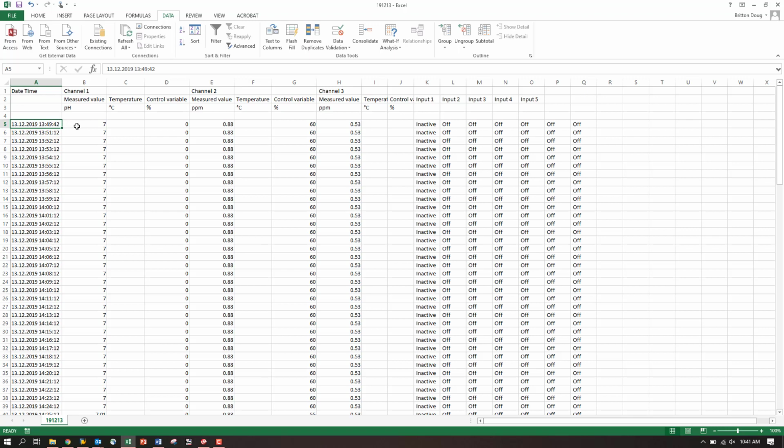Our channel 1 had a pH of 7. It wasn't controlling because our set point is 7, so the pump was not pumping. Our channel 2, which is our free chlorine, had a reading of 0.88 ppm. And at that point, we were controlling 60% to chlorinate.